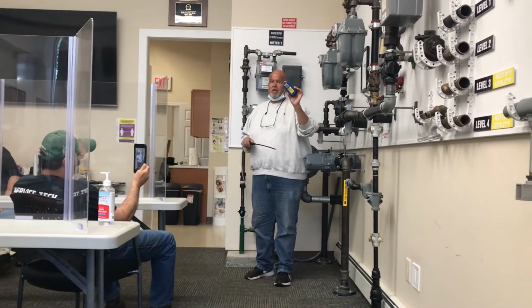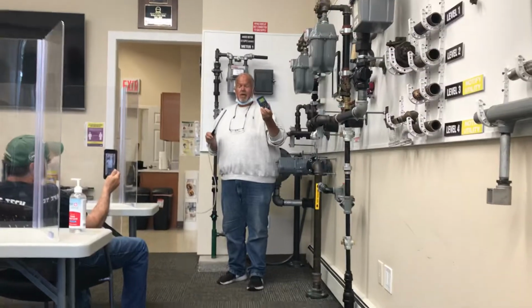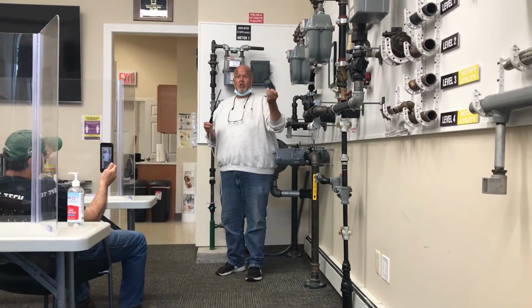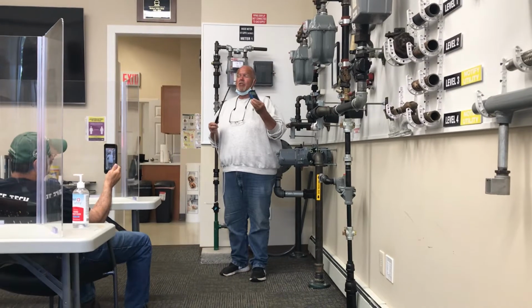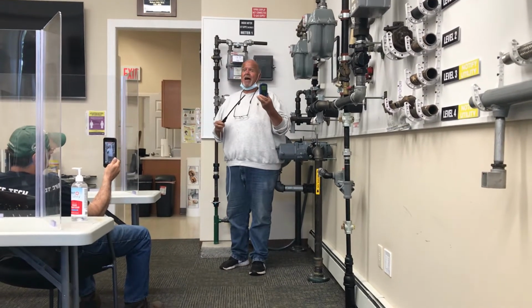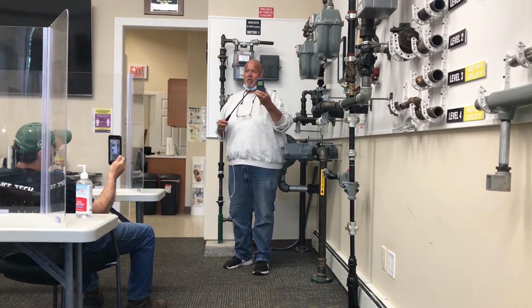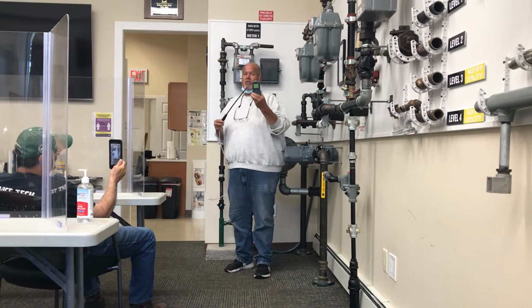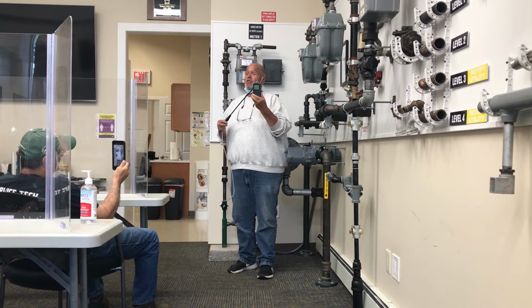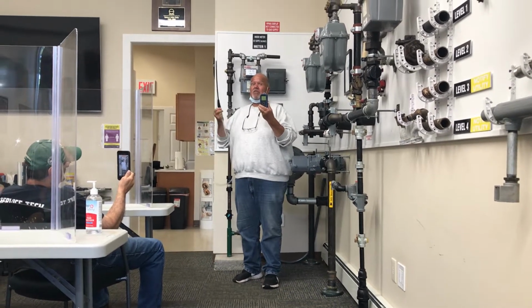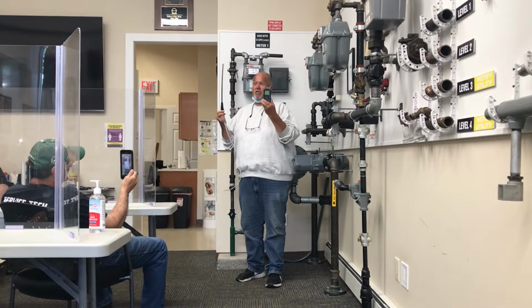Steps necessary to go through before you start your inspection. Outside the building, always do these outside the building, never inside the building, right? You never turn the machine on inside the building because the machine is going to zero itself out to the atmosphere and say this equals 0. So this always has to be done in fresh air.